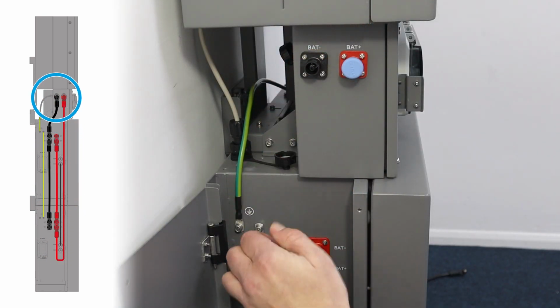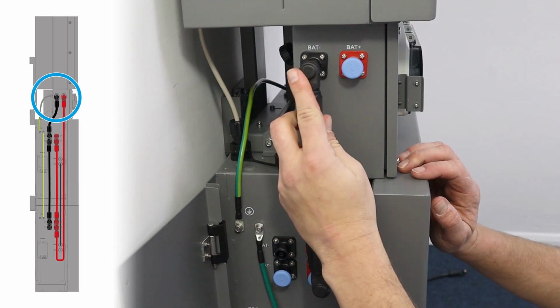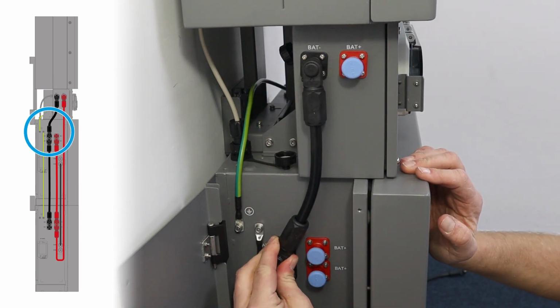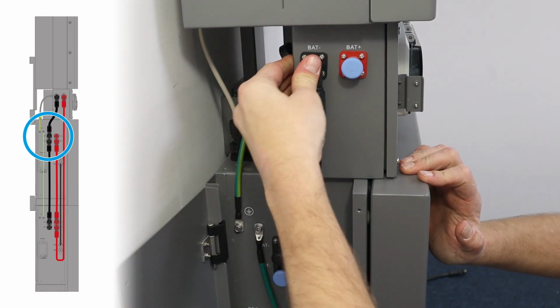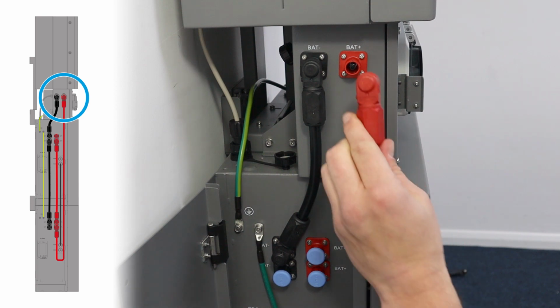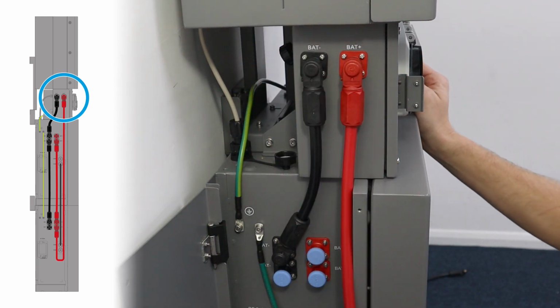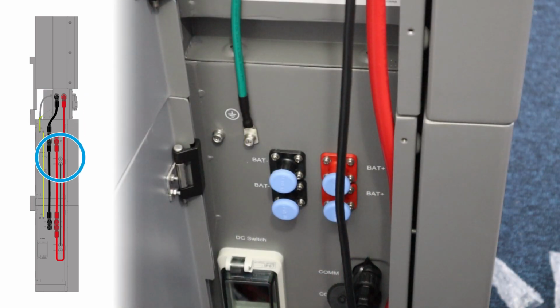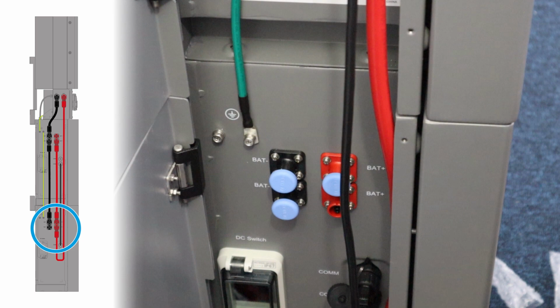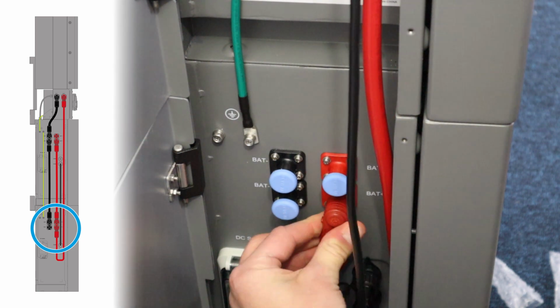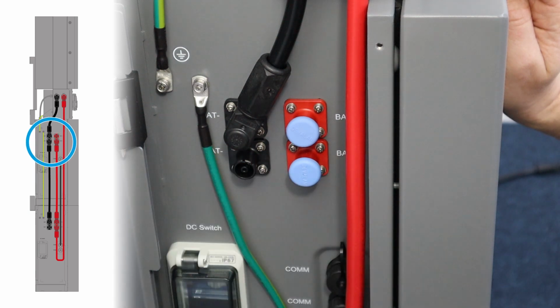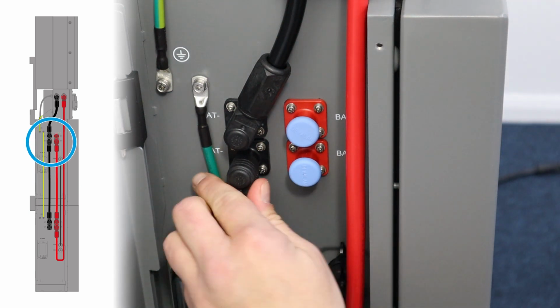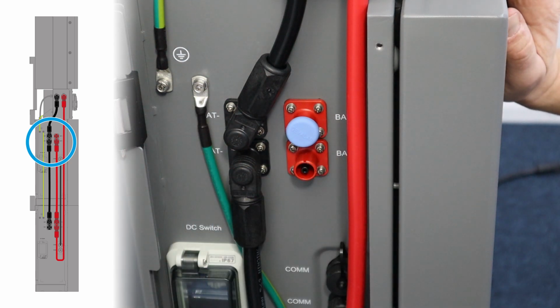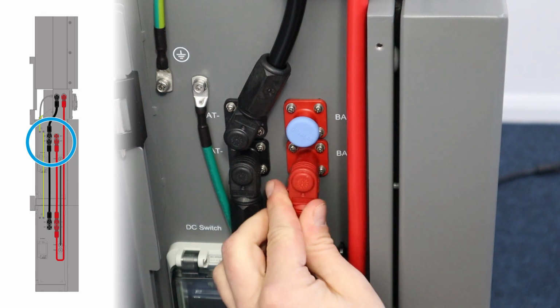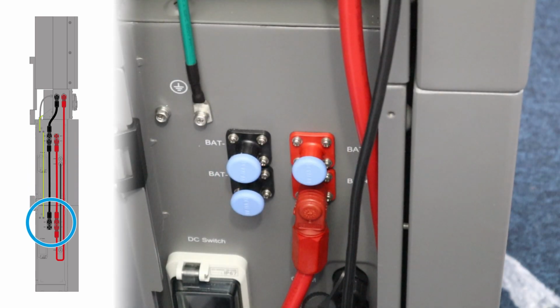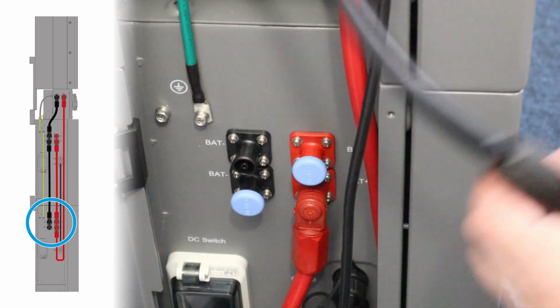As for a single battery installation, connect the short negative lead between the inverter and battery 1. This time, connect the inverter with the long lead to the bottommost positive terminal on battery 2. Then connect the bottom 2 negative and positive terminals on battery 1 to the top negative and positive terminals on battery 2.